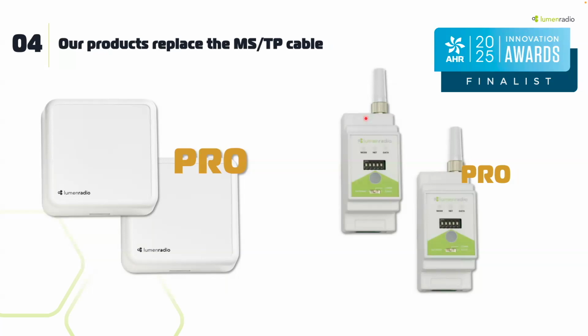In a network, you can have up to 100 wireless nodes, but for a proper BACnet network using controls, we recommend keeping it to 25 BACnet devices on that wireless network. Above that, it gets a bit wonky - you'll have a harder time getting a stable, fast network. We're working on making it stable above 25, but we're not there yet. So I'm just trying to be transparent that wireless is not a silver bullet. It will not give you super fast speeds, and it will not give you infinite range.